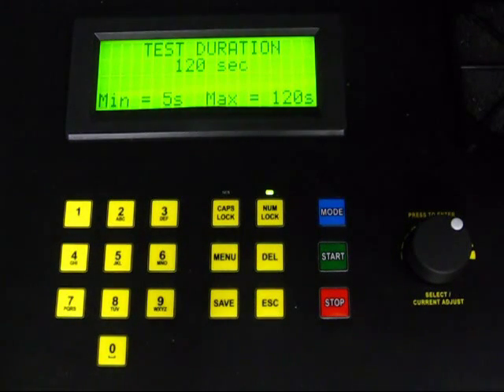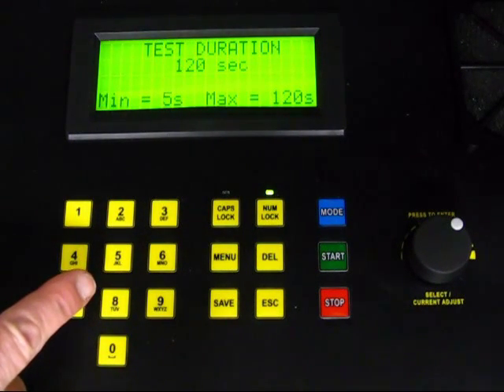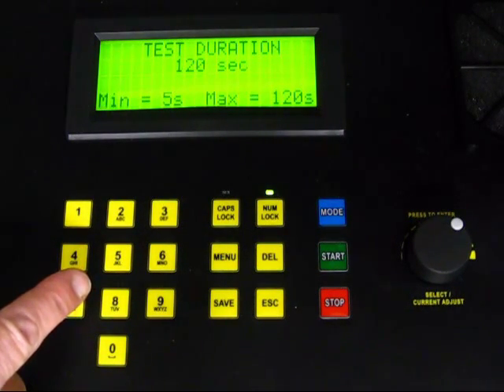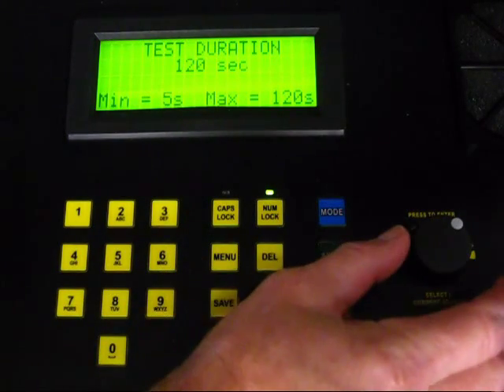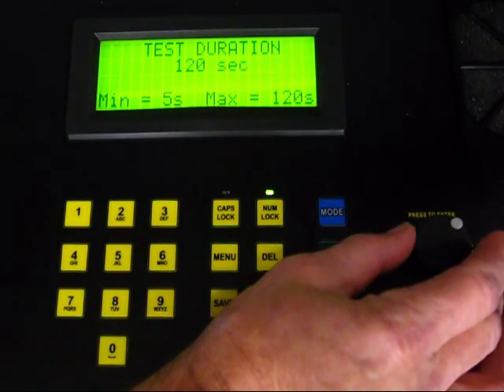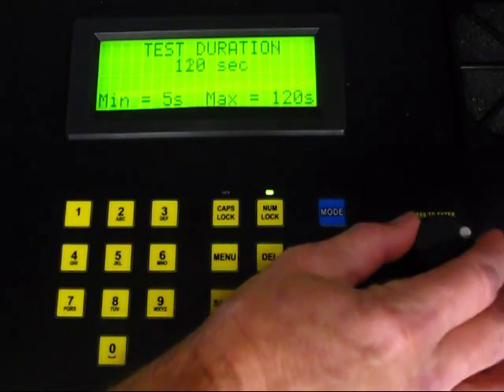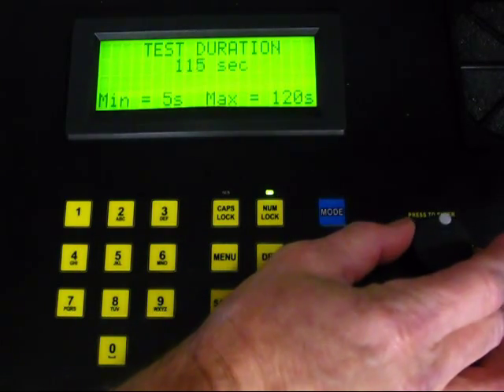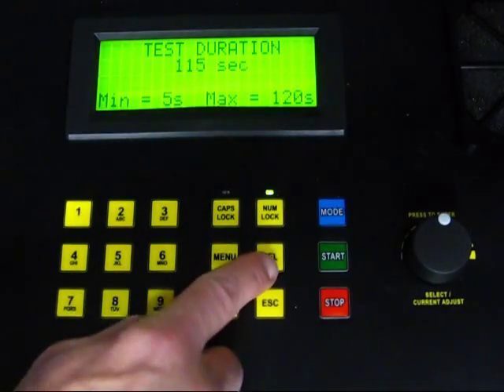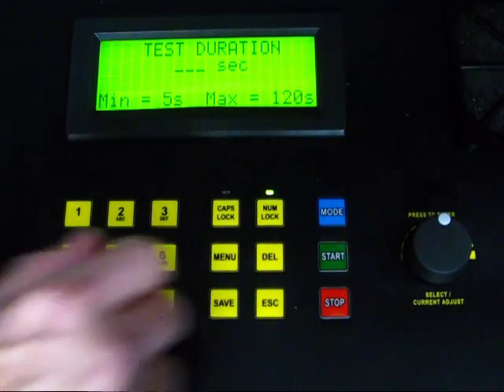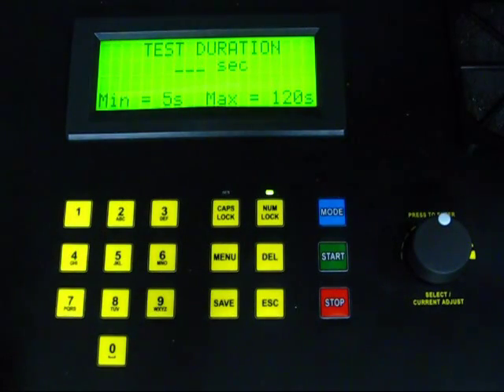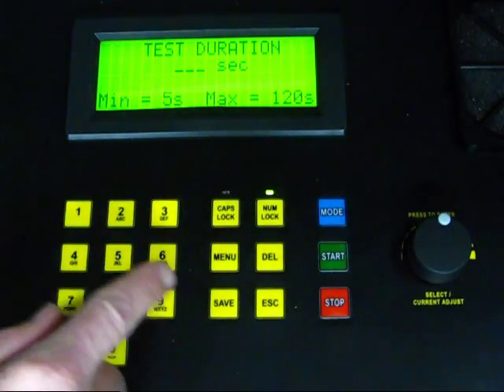There are two ways you can enter the duration. One is by using the keypad to type in the number of seconds. You can also turn the rotary knob to select a higher or lower number. For timed test, the minimum duration is 5 seconds and the maximum is 120 seconds. In our demonstration, we will select 20 seconds.